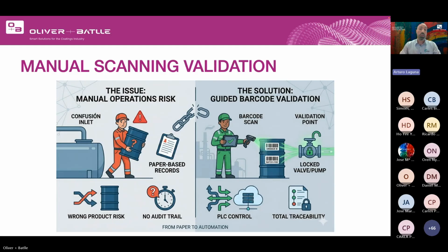Our solution was simple, and we've applied it at many sites: validation before action. We integrate barcode scanners directly with the plant control systems, the PLCs, and the rule is, if there is no correct scan, there is no action. For example, imagine a truck arrives at the factory for unloading — our system keeps the control element, the pump or valve, locked.